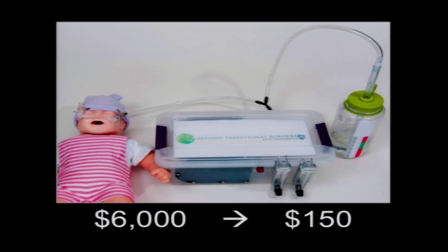The genius of the system is that the pumps that deliver the air to the baby are aquarium pumps. Aquarium pumps are designed to run continuously for years on end and not break. This is what they need to be able to do in the developing world. If they break, it's a simple diaphragm. If that rips, you have to replace it, but it's less than $1. And you unscrew the pump and you pop a new diaphragm on and it will work from there on out. So that was a really clever potential solution.